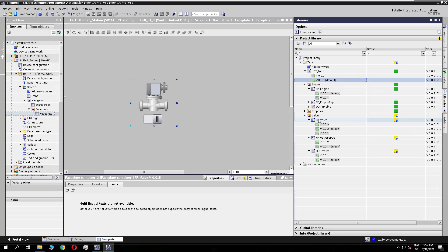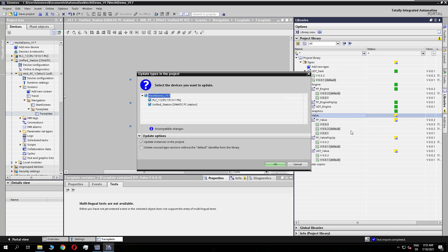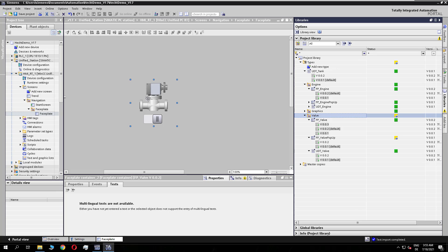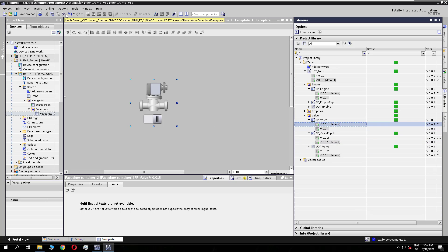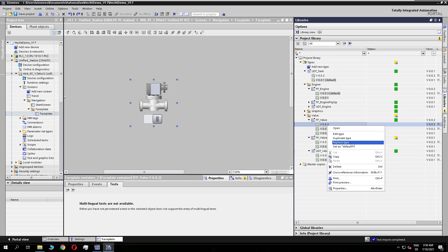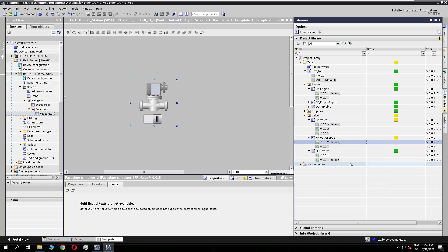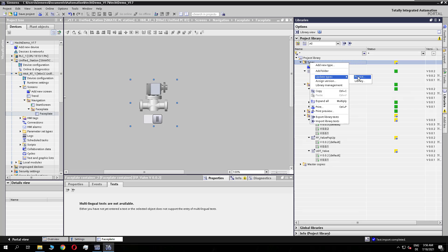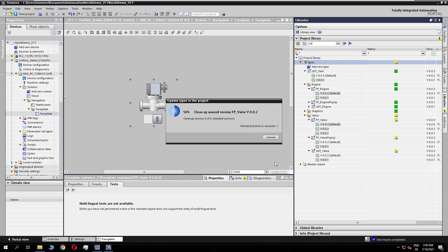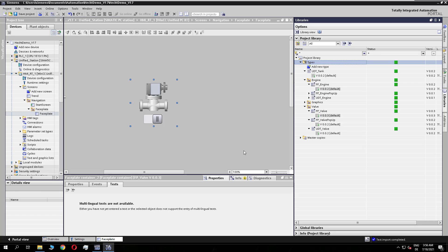The tank previously used valve version one, and updating means we used valve version two with UDT valve version one, causing the inconsistency with the pop-up calling version two inside version three of the valve. Deleting version three resolves it — I use the default types from the library in my project. To go to the higher version — face plate version three with pop-up version two and UDT valve version two — rather than doing it step by step, you can update all complete types and delete unused types in one cleanup, and everything is green again.